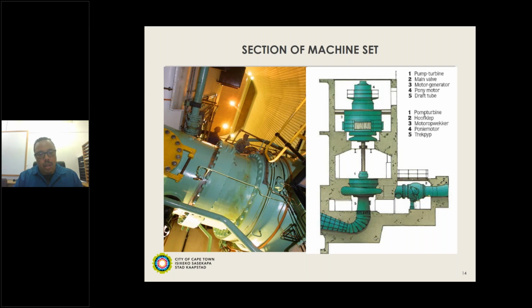Then when it gets to the power station, it splits or bifurcates into shaft A and shaft B. And then it further splits again into unit 1 and 2 and unit 3 and 4. So the term that we usually use there for the split is referred to as the bifurcation of the penstock system. So on the right hand side of the drawing labeled as 2, that's your MIV. So each individual unit will have its own main inlet valve, and simply put, that is the valve that controls the water in and out of your machine.